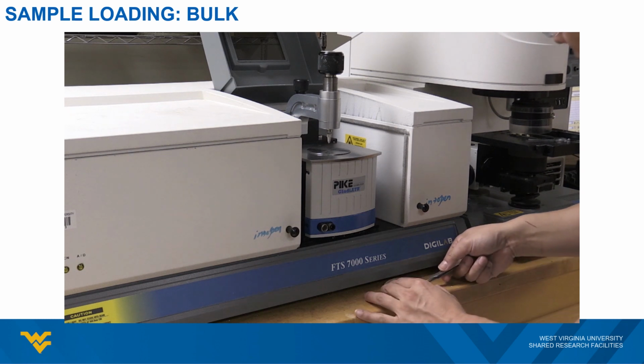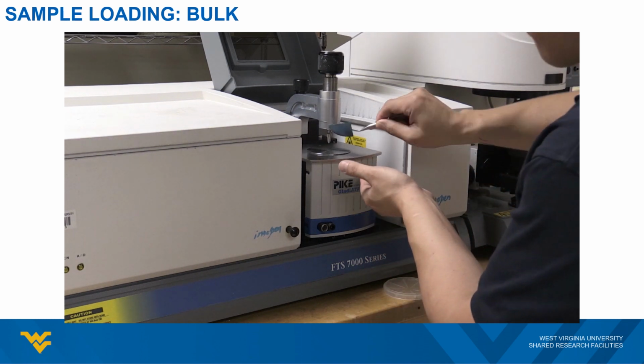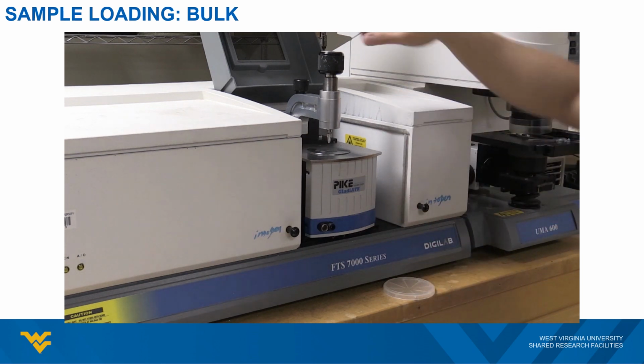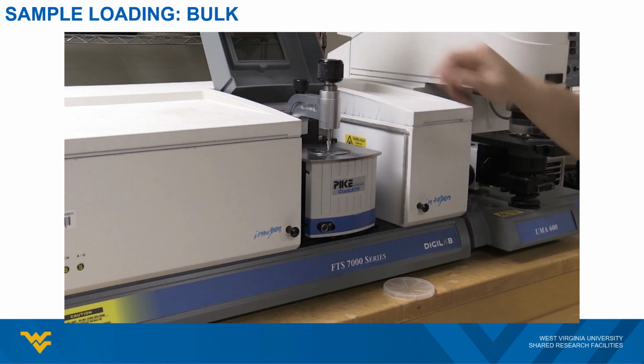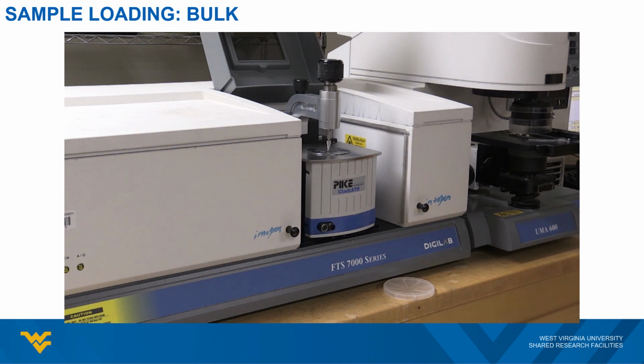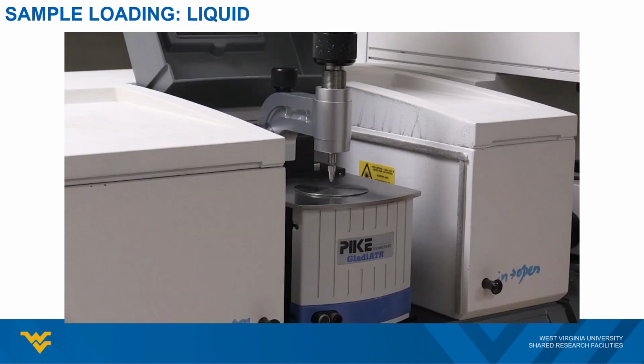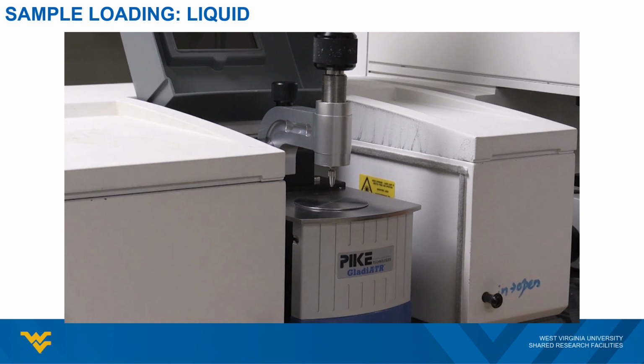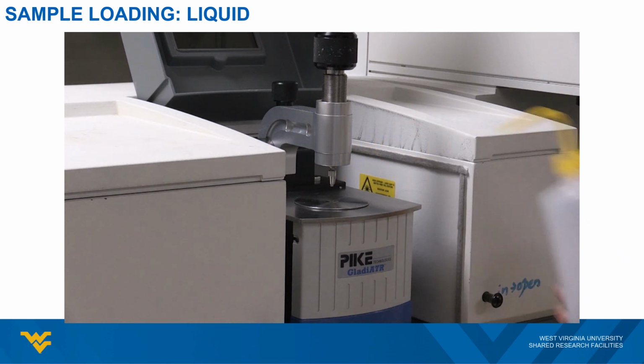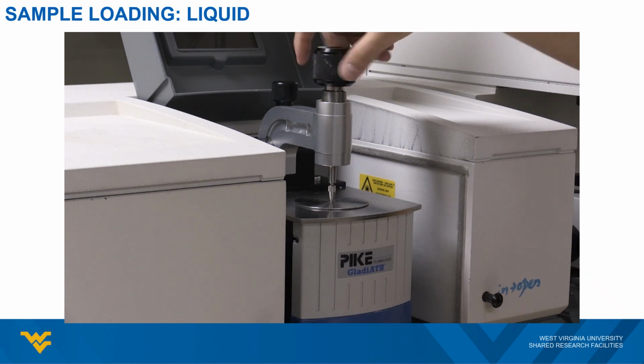For bulk sample, like films on substrate, we basically follow the same procedure. Remember that the IR beam will interact with the sample through the diamond window. So the surface of interest needs to face down to the window. For liquid sample, again, the procedure remains the same. However, ensure that you only apply a limited amount of liquid, just enough to cover the window. Be careful to avoid spilling an excessive amount of liquid across the entire module.